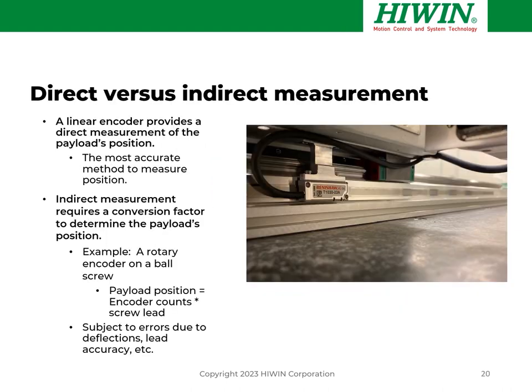Another important concept is how we make our measurement — direct or indirect. A linear encoder is a device that provides direct measurement of the payload's position and is the most accurate method. It measures directly without any intervening elements introducing errors. An indirect measurement requires a conversion factor and involves intervening elements to determine payload position. For example, in a ball screw system with a rotary encoder, payload position is a function of encoder counts and the lead of the screw — subject to errors from deflections, inaccuracy in the screw lead, manufacturing tolerances, and wind-up.